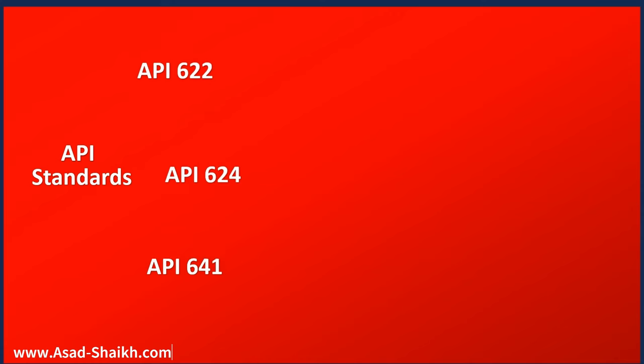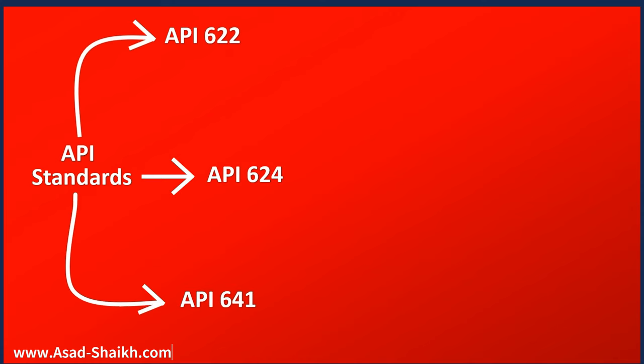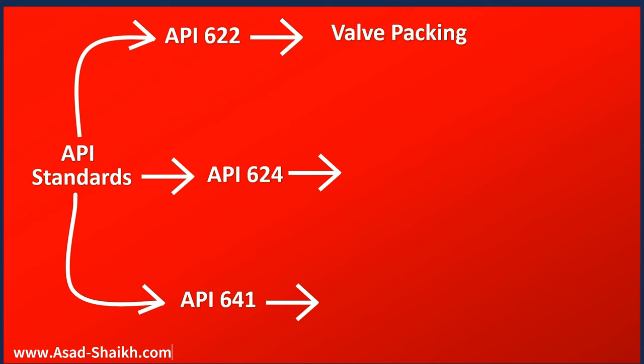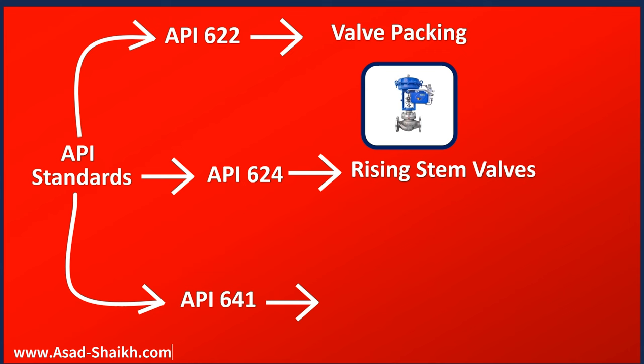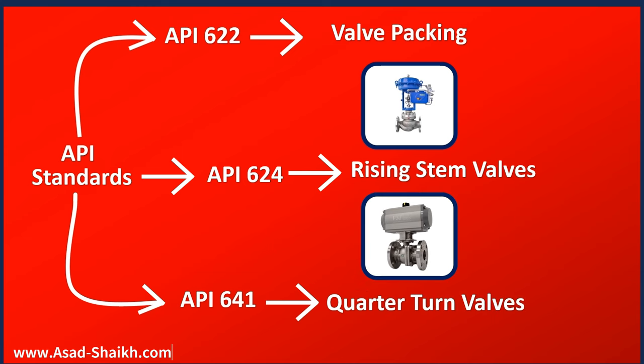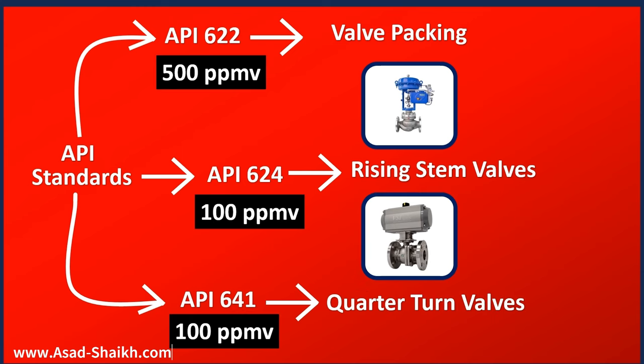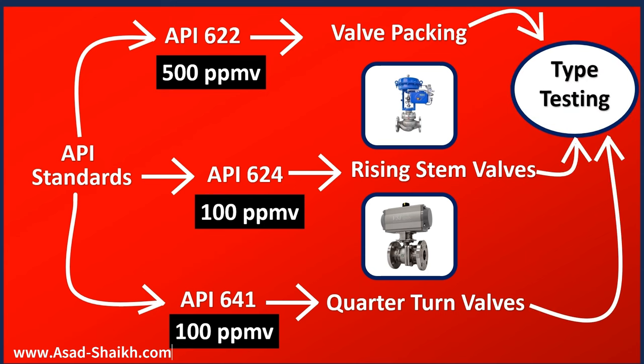The API standards are divided into three important standards used throughout the world: API 622, 624, and 641. API 622 covers the valve packing itself. API 624 covers rising stem valves — for example globe valves and gate valves. API 641 covers quarter-turn valves. The emission criteria are comparatively stricter: 100 ppmv for valves and 500 ppmv for packing. These standards will likely get even stricter in the future. Importantly, all three of these standards fall under type testing. Only for production testing do you use ISO 15848 Part 2.